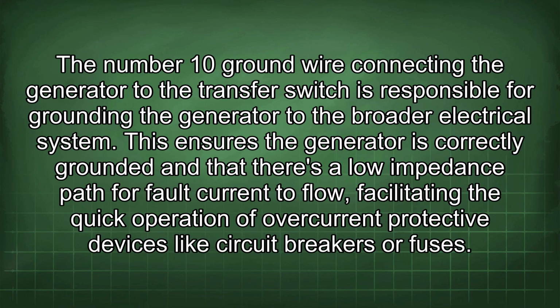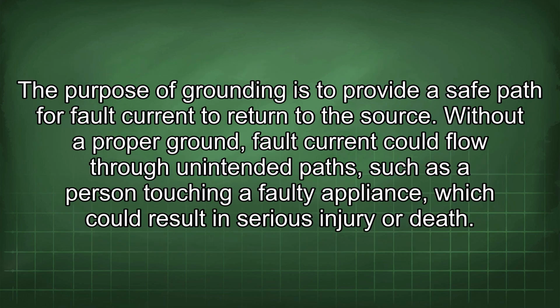The number 10 ground wire connecting the generator to the transfer switch is responsible for grounding the generator to the broader electrical system. This ensures the generator is correctly grounded and that there's a low impedance path for fault current to flow, facilitating the quick operation of overcurrent protective devices like circuit breakers or fuses. The purpose of grounding is to provide a safe path for fault current to return to the source. Without a proper ground, fault current could flow through unintended paths, such as a person touching a faulty appliance, which could result in serious injury or death.